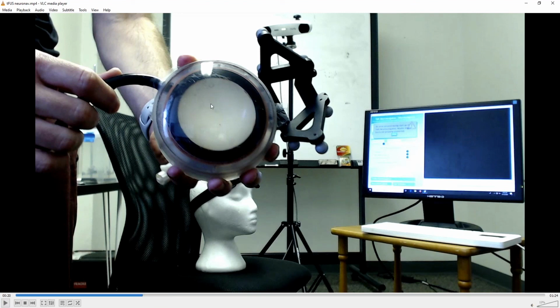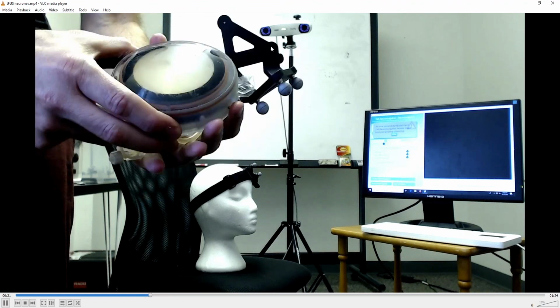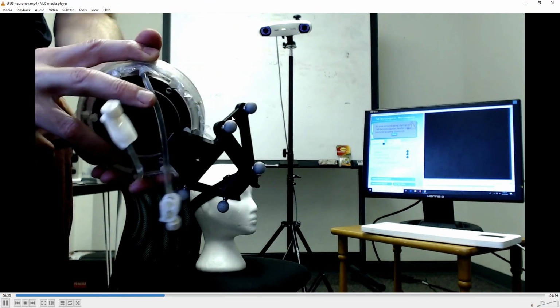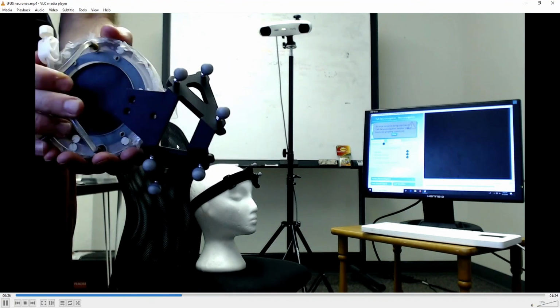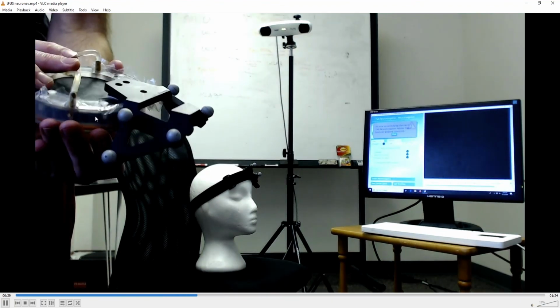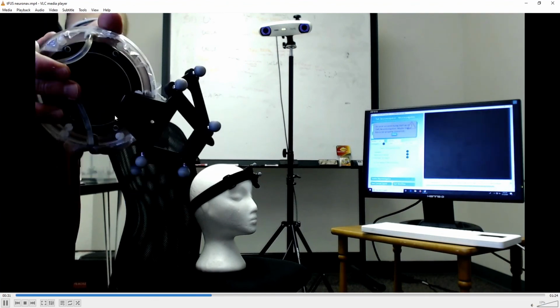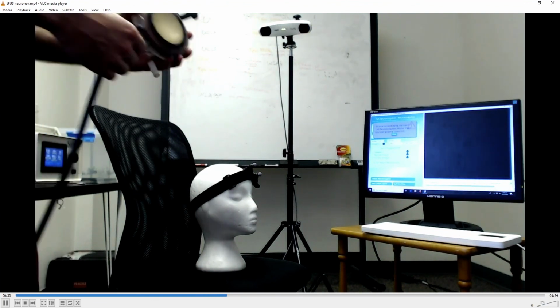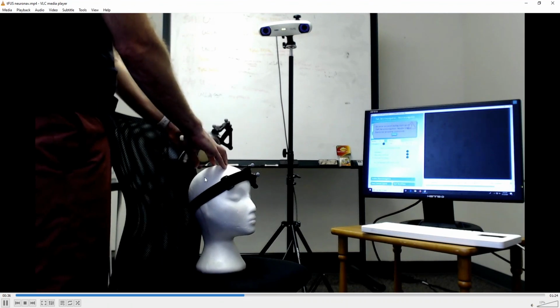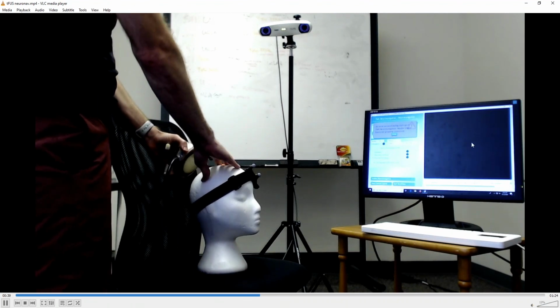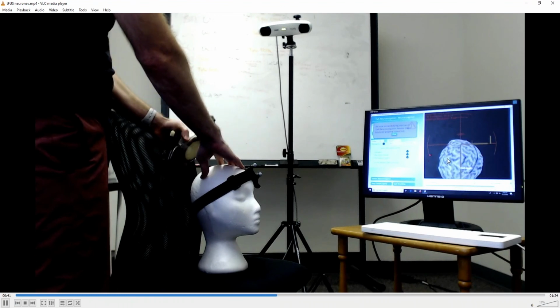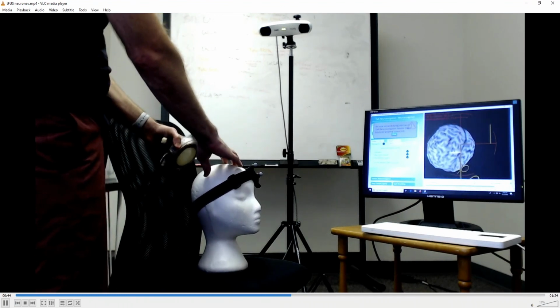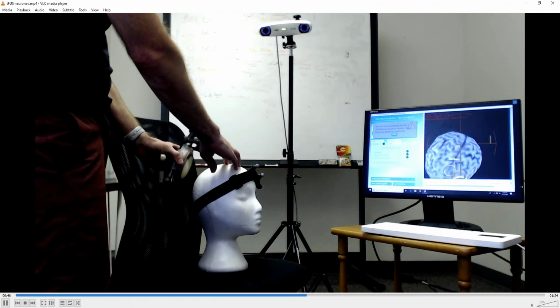They can lay on this transducer in the MRI scanner. This is MRI compatible. It's very comfortable to put on the back of the head. What you see is that camera, the neuronavigation camera, can actually see this part of the transducer. We've aligned it so the camera knows exactly, relative to this geometry, where the center of the transducer is. Now I've got an average MRI fed into the machine, and once the camera sees the transducer, you see the subject's brain. The orientation is flipped because I've got the transducer upside down.